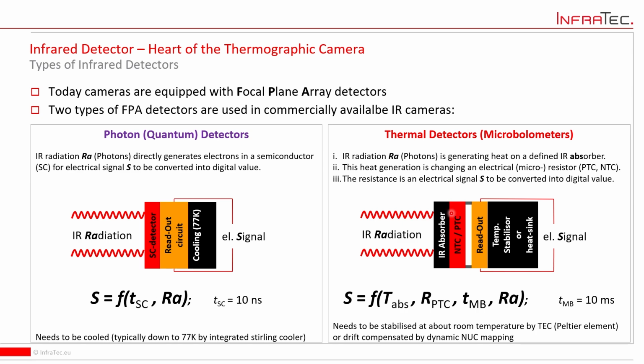That's done with temperature-dependent resistance. So they can change the resistance, either go up or down, depending on the temperature change. And what we have to do then is determine the resistance. That's done by running a tiny bit of current through them to get a voltage drop, which gives you the electrical signal, again, with the help of calibration curves, turned into a temperature measurement.